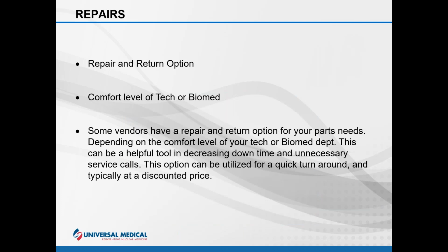I want to mention repairs real quick. This is an option that can be used. It doesn't seem to get used very often. Check with your preferred vendor to see if they offer this. This is something that vendor to vendor would typically use, but this can be a helpful tool depending on the comfort level of the tech or biomed department. Your vendor might offer this option in certain circumstances. There are situations that can be done, let's say, within a few days. A part can be shipped to the vendor, and if applicable, can be repaired within a day or two and shipped back to the customer.